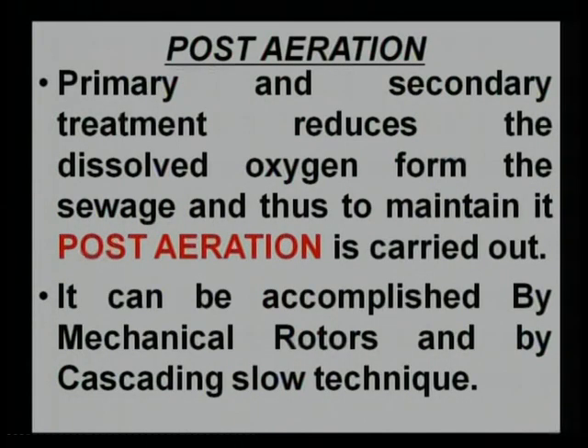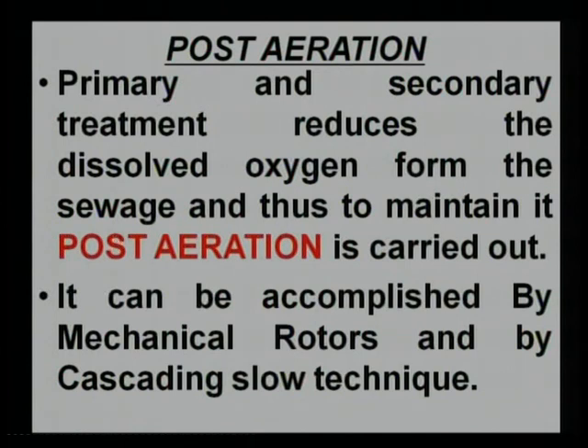Advanced treatment includes removal of suspended solids, activated carbon treatment, chlorination, nitrogen removal, and phosphorus removal. After this, if the dissolved oxygen is depleted, we need to increase it. The method for this is known as post-aeration. Primary, secondary, and even advanced treatment reduces dissolved oxygen from the sewage, and thus to maintain it, post-aeration is carried out. It can be accomplished by mechanical rotors and even by cascading slow technique.